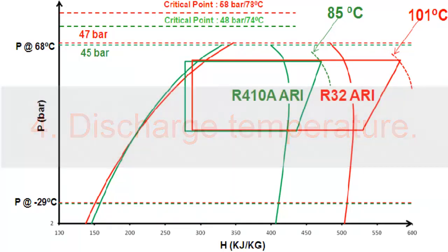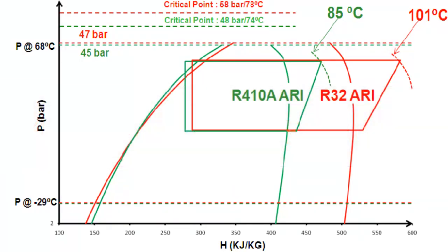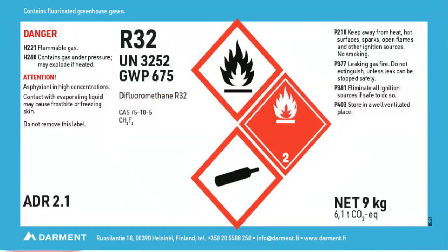4. Discharge Temperature. With this change, the refrigerant temperature at the compressor's discharge outlet will notably increase, potentially affecting the compressor's lifespan. 5. Safety. It is not advisable for safety reasons to switch from R410A to R32 without the manufacturer's authorization, even though R32 is only slightly flammable.